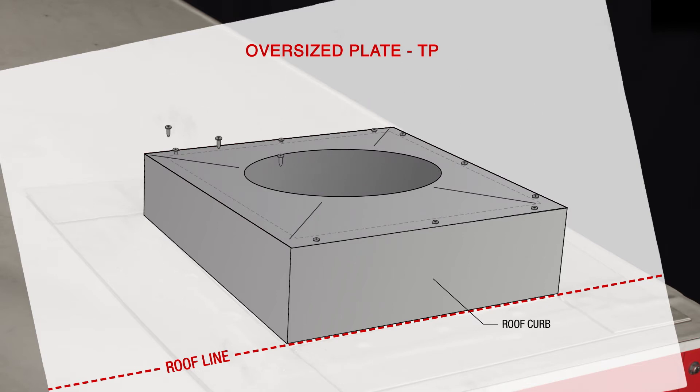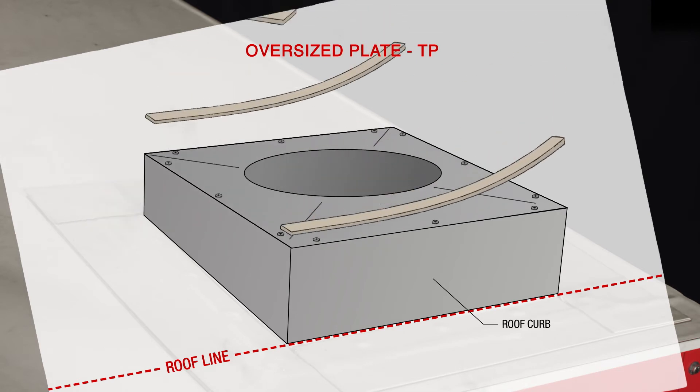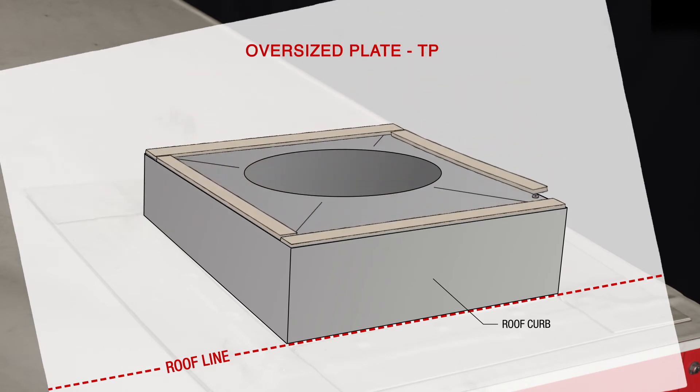You can then secure the plate to the top of the curb using three self-drilling pan head screws per side. Lastly, add the included gasket material to the edges of the plate as shown. It is acceptable for the gasket to sit over the fasteners.